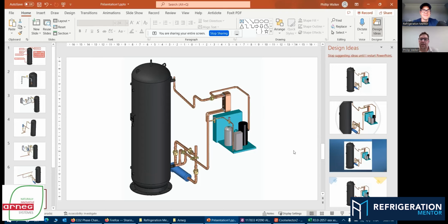So here is our backup unit, totally critical. Typically it is put on a generator. Either we could supply the generator, or it goes on the building generator. So essentially, on a critical instance where we lose power, the backup unit will kick on. We have a plate heat exchanger, and it's going to maintain the pressure inside the flash tank. Why is this absolutely necessary? We just talked about maintaining pressure inside the flash tank, because we have all these pressure reliefs here, and our pressure relief typically on a supermarket design is 650 PSI. So if we start to exceed that, we're going to start to lose CO2.